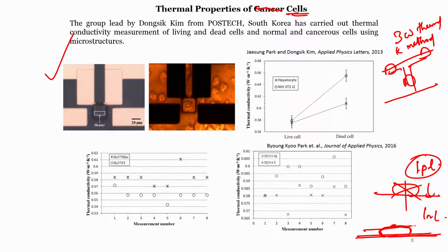Let us say this is the surface of the tissue and we are seeing it from the top like this. So, we will have a heat source, we have temperature sensors which are again coils only, but can double up as temperature sensors if they are not actively heated. One temperature sensor is actively heated, okay, and it is actively heated, and the other two detect the thermal conductivity through the surface of the cell.